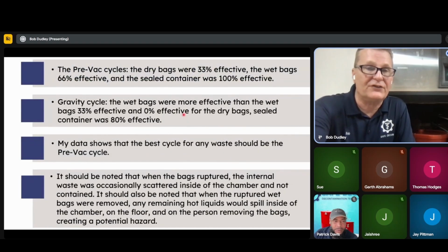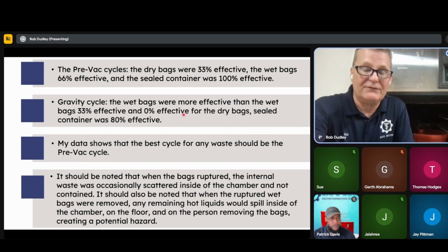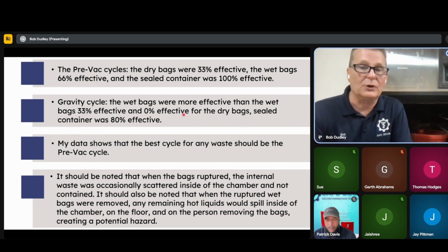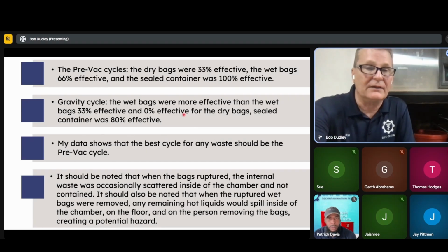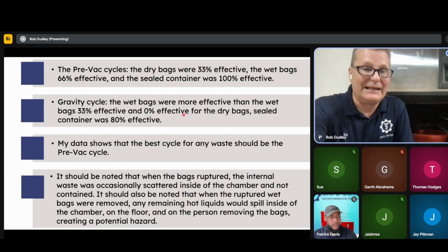I'm going to breeze through this. On the pre-vac cycle, the dry bags were 33% effective, wet bags were 66% effective. The Safe-Decon container was 100% effective. On the gravity cycle, the wet bags were more effective than the dry bags, which is backwards since it's supposed to be dry bags. The wet bags were 33% effective, the dry bags were 0% effective. The seal container failed on that one as well.